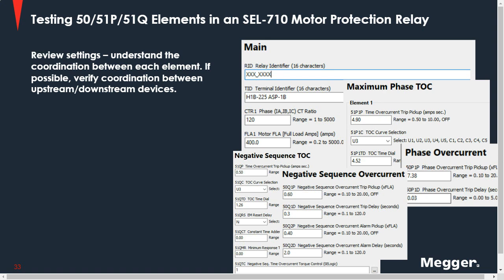I know that it's often taught that as a test technician, you should just test whatever settings you're issued. But what I think gets mistaken here is that you, as a test technician, should not take the liberty of making changes to the settings. That's the big thing.